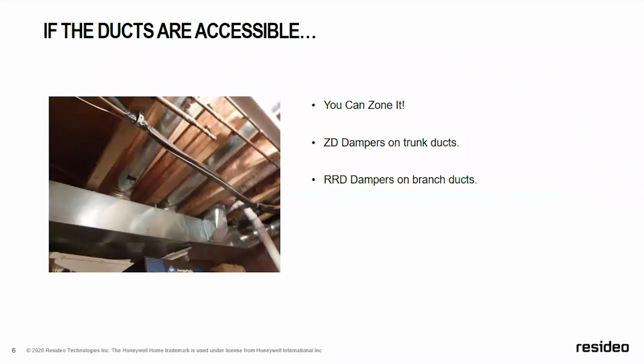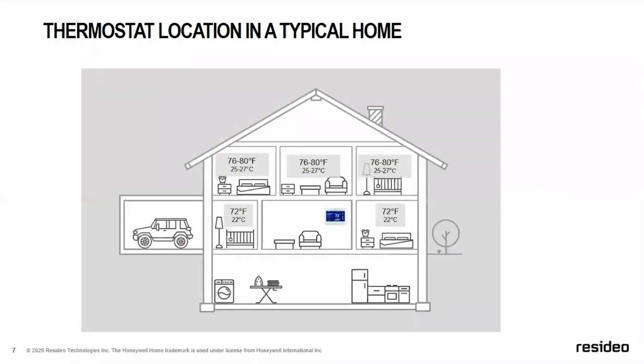If the ducts are accessible, you can zone it. You can use ZD dampers on the trunk ducts, RRDs on the branch ducts. We'll get into that a little bit further down the line. Typically in a house, your thermostat is on a 2-story house anyway. Thermostat is generally located on the first floor, living room, dining room, hallway. And typically you're gonna have it at 72 degrees. You're gonna get, in this slide, 8 degrees of rise, but in practical sense, it's more like 10 degrees of rise.